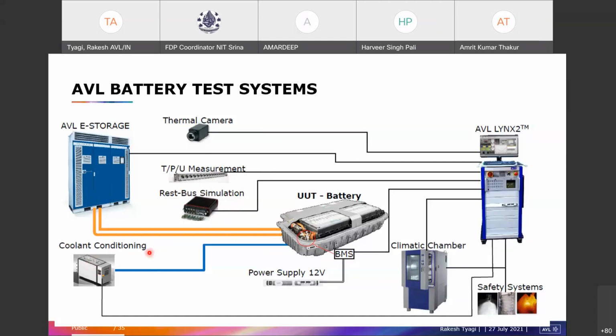Coolant conditioning is a device that's common, depending on your model. If your cooling is air cooling, no problem. But if it's oil cooling or coolant cooling, some kind of conditioning device is needed. The purpose of conditioning is to maintain temperature, for example in centigrade. So coolant will always be flowing through your UUT, controlled by heating or cooling, keeping the UUT's temperature constant. This conditioning unit is the same whether you're using a coolant-cooled or liquid-cooled battery, an e-motor, or an inverter - its purpose is to keep the temperature maintained.